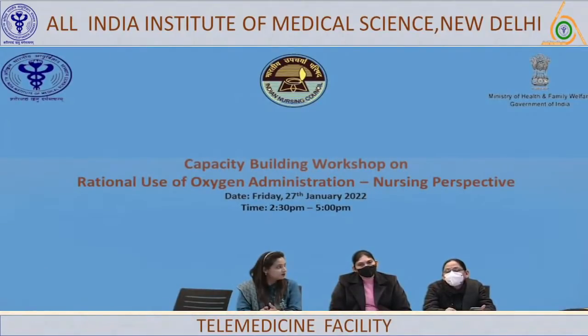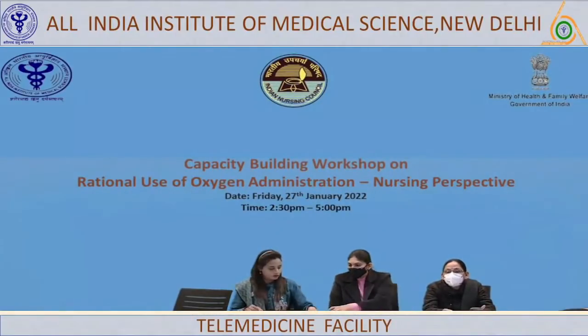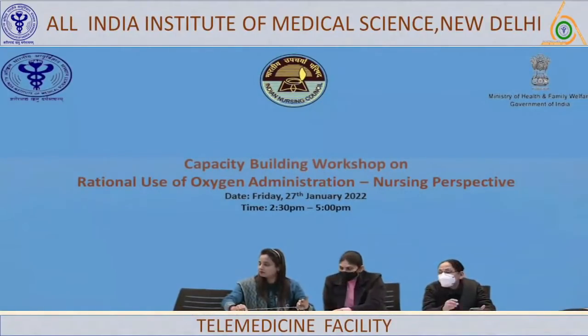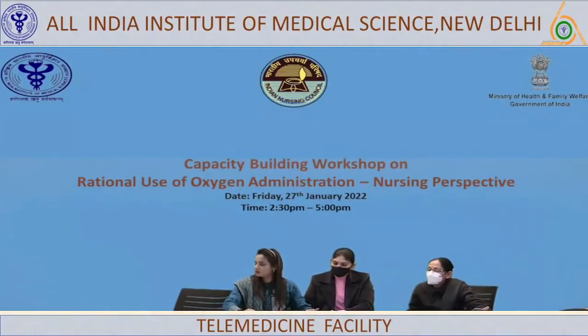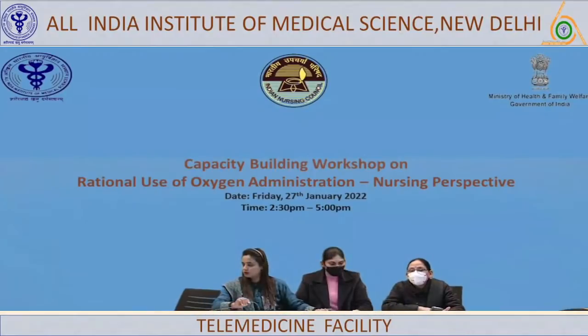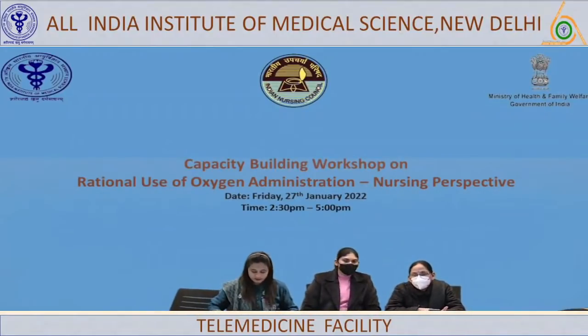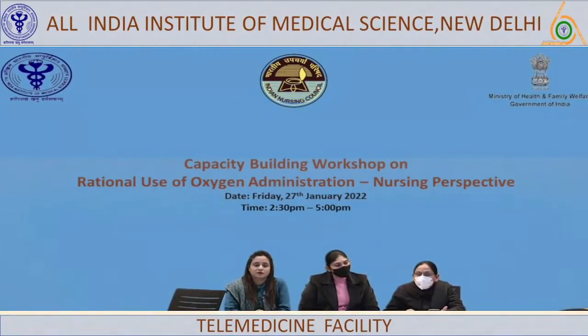Thank you, ma'am. As we have seen, in this pandemic time the use of HFNC devices has increased, so cleaning and disinfection is a major concern. First of all, like the ventilator, we have to clean the device. It has an outer surface and accessories. The accessories are usually single patient use. So after use on one patient, we have to dispose of all the accessories, like the tubing, the nasal prongs, the water chamber, and the humidifier chamber, in a designated biomedical waste bin.